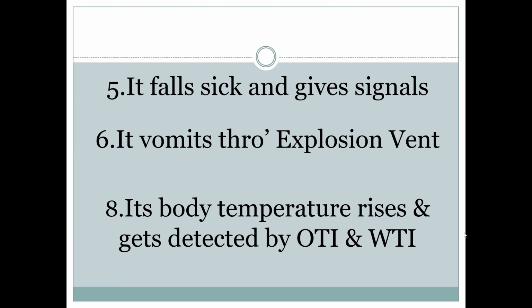Our body temperature also rises because of some malfunction, and likewise, if any malfunction happens to the transformer, its temperature also starts rising, and that can be detected by a temperature meter, a thermometer like ours. There is the oil temperature indicator, with which we can measure the oil temperature, as well as the winding temperature indicator. And finally, it dies when its core and winding fail. We call the transformer dead.